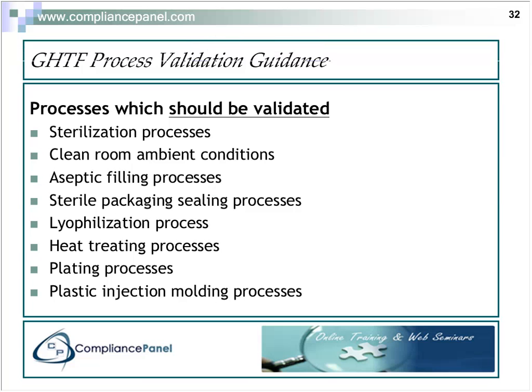I'm going to add two here that are not in the GHTF document, which the FDA does insist include welding and soldering. Soldering processes must be validated. So as we're producing printed circuit boards, for instance, for electronics in our products, those processes must be validated.